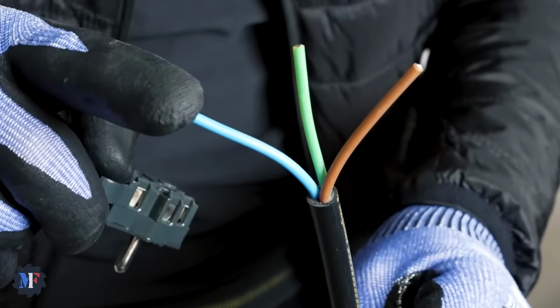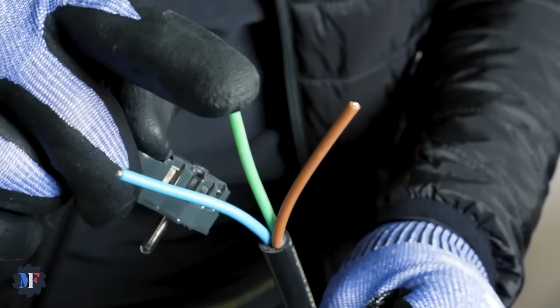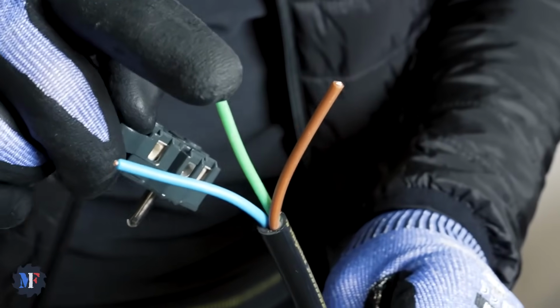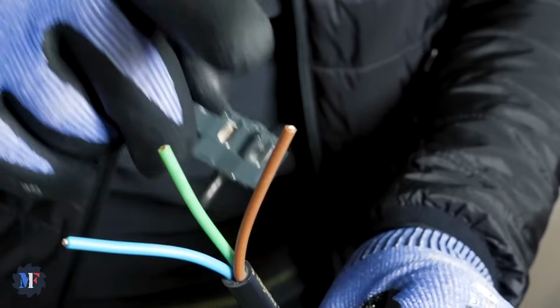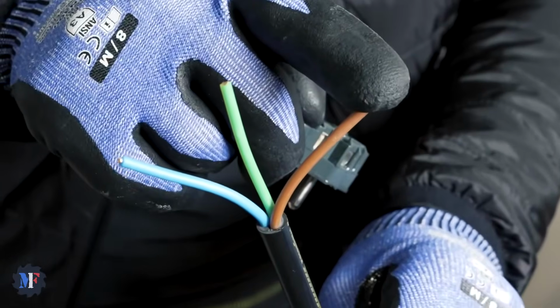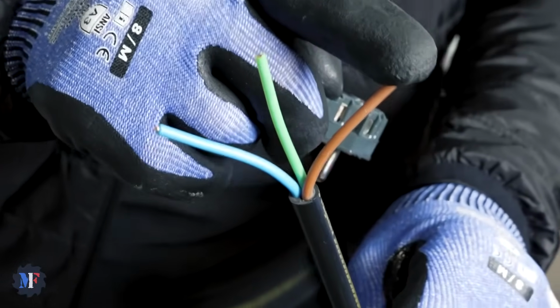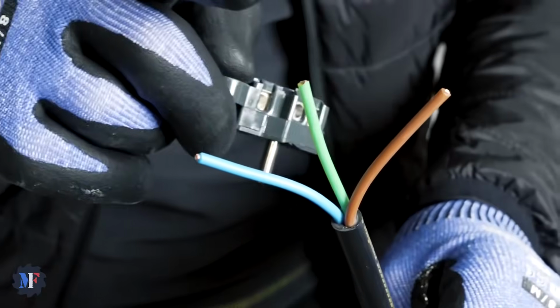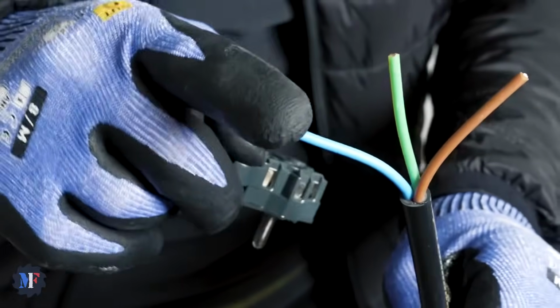The neutral is always blue, that's mandatory. The ground is yellow and green as well. It's mandatory to respect these colors and of course to connect them properly. Then we have the phase, which can be brown, black, red, or purple, it doesn't matter. But the 2 colors you must respect are yellow and green for the ground and blue for the neutral.